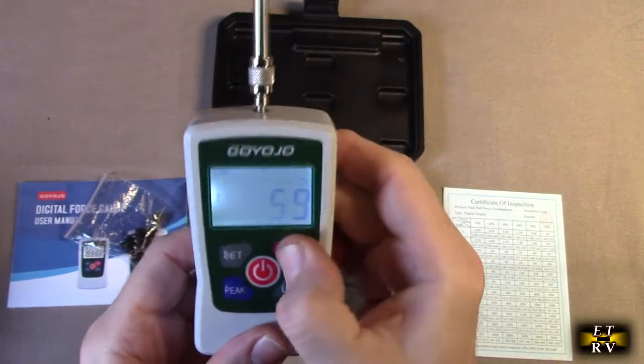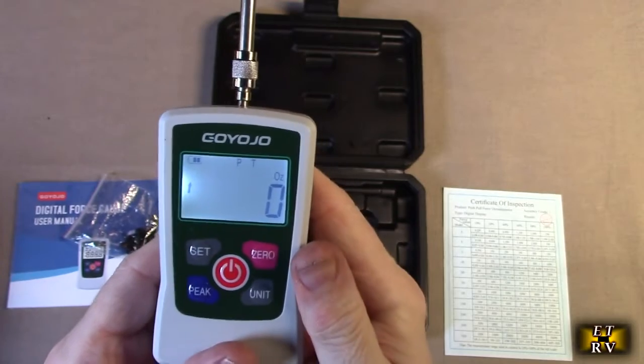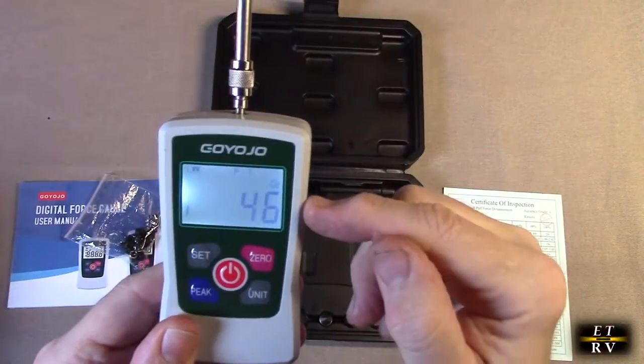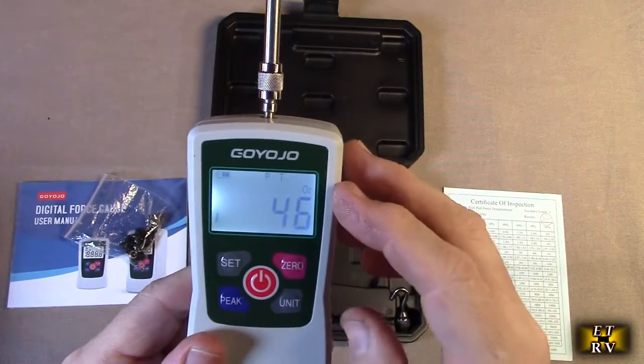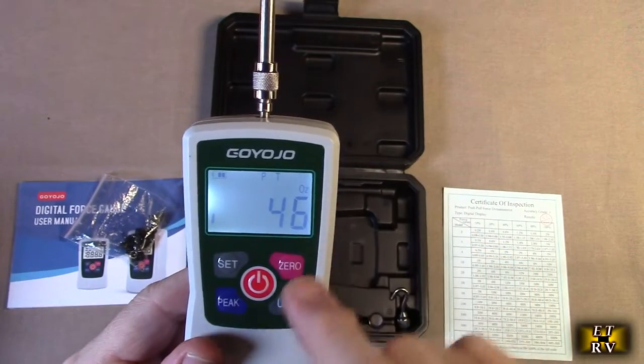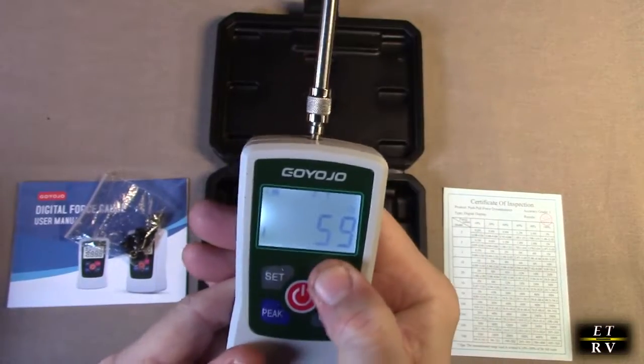There's another mode labeled P&T — a timed method described in the manual where you set how much time you want between the movement and when it locks. That would be really handy if you're doing a repetitive operation based on time and want to measure forces over time. You can zero that out and lock it in place just like the other modes.